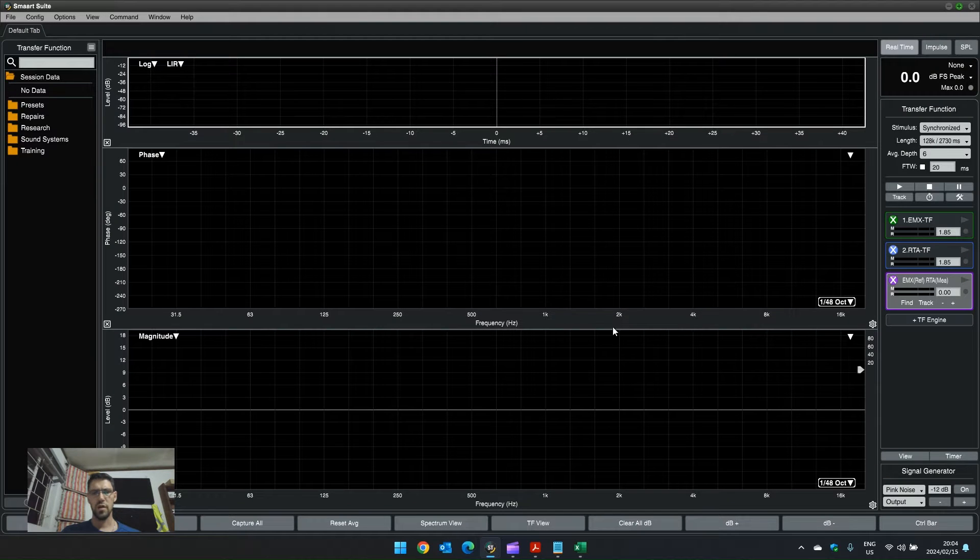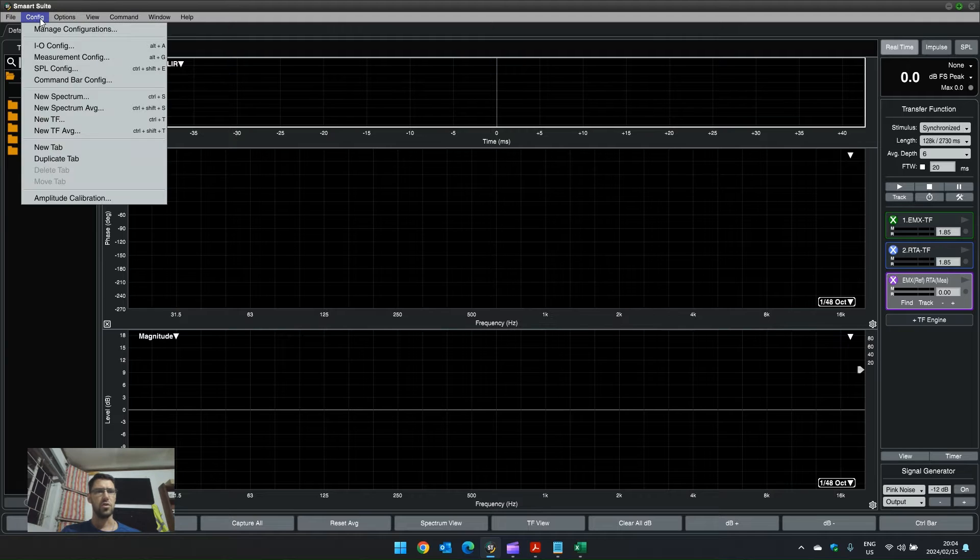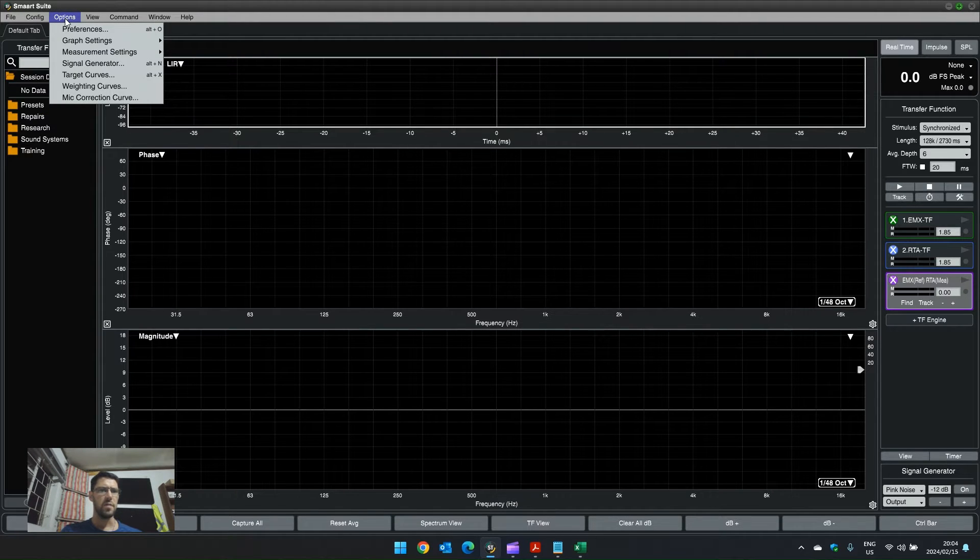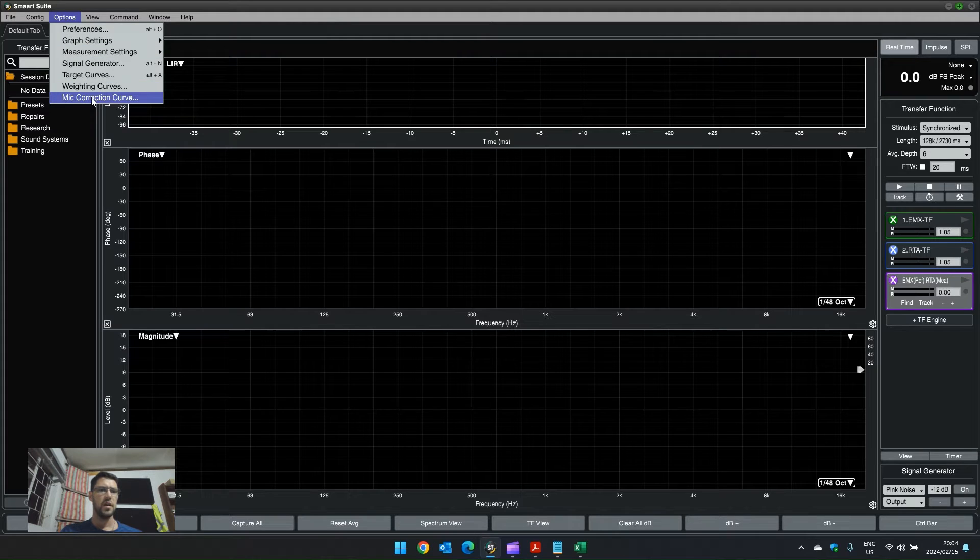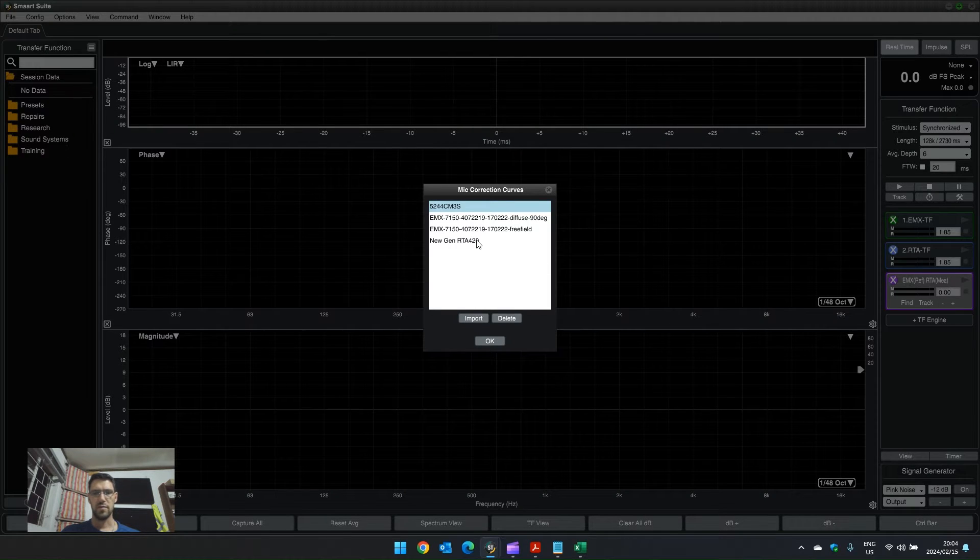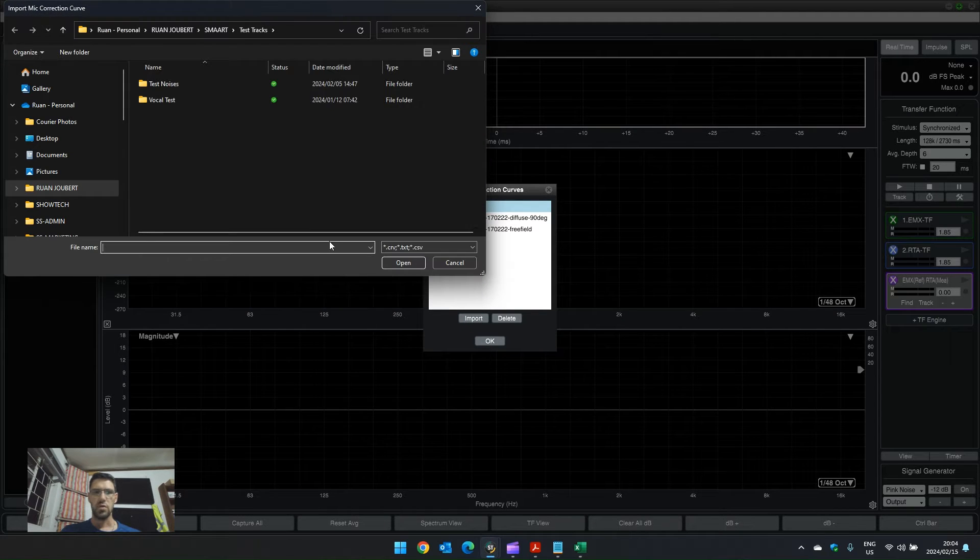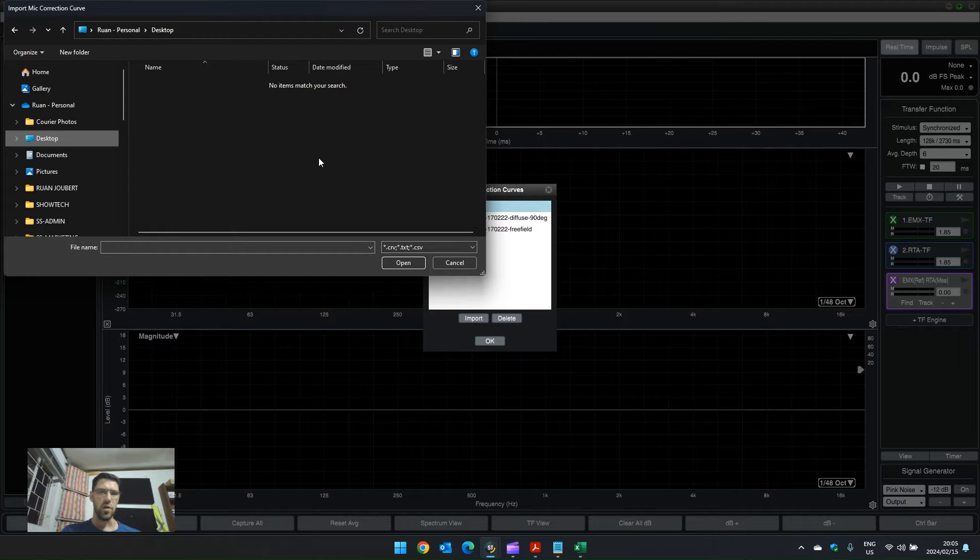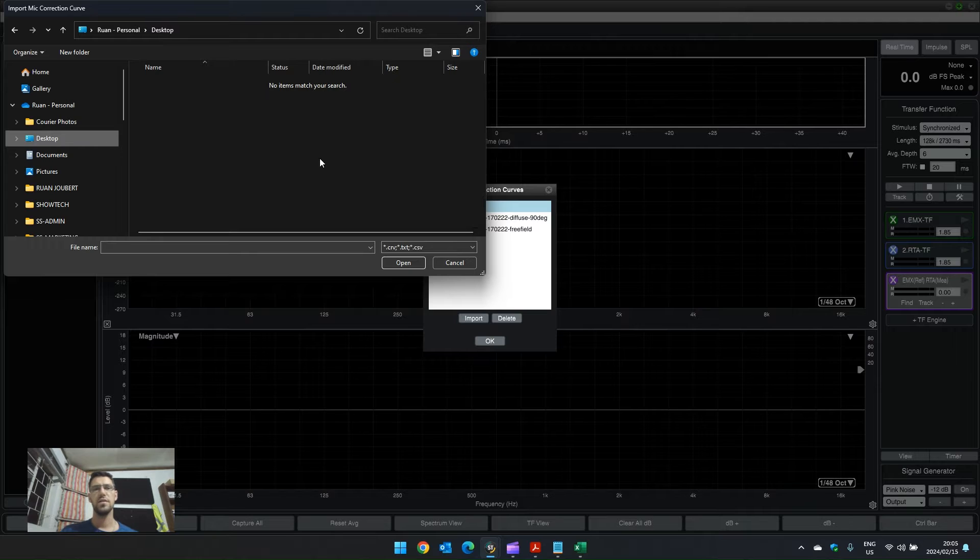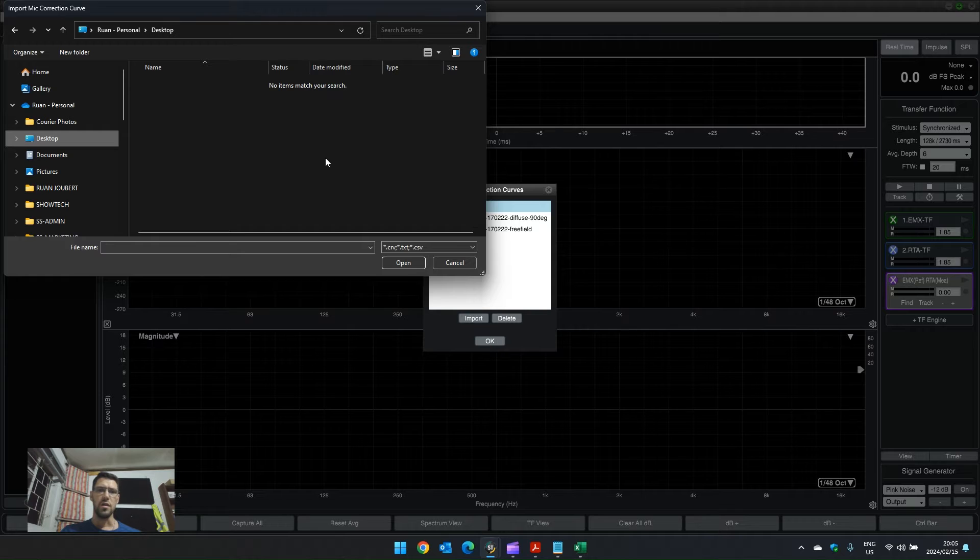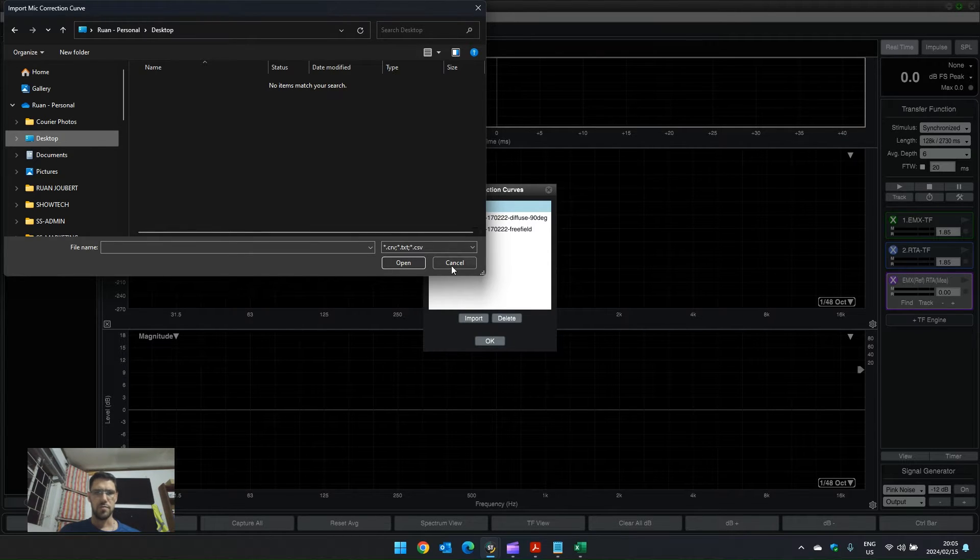In Smaart, we have the option to import mic correction curves. When we go to options and mic correction curve, I already have some of them imported here, but we can choose to import correction curves from somewhere on our desktop. Usually manufacturers will supply these on a website download link, or they'll email it to you if you request it with the serial number of the microphone that you purchased.